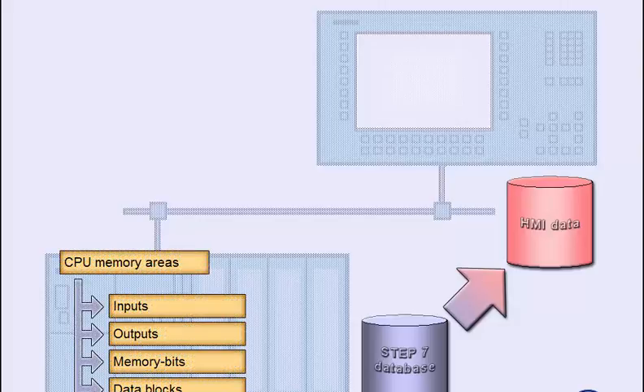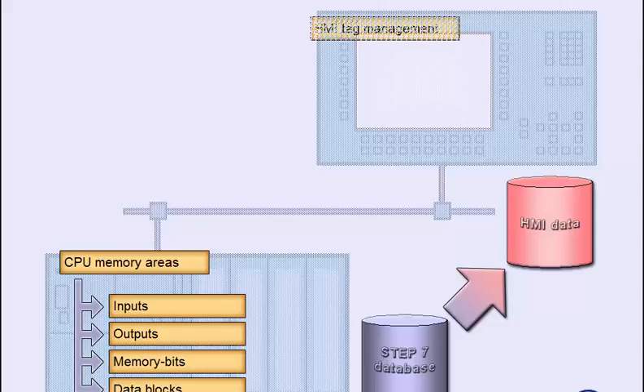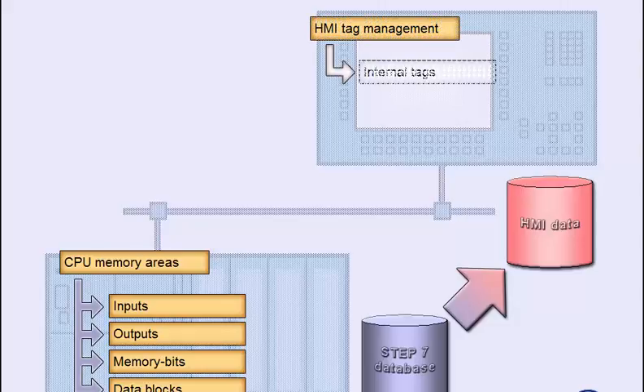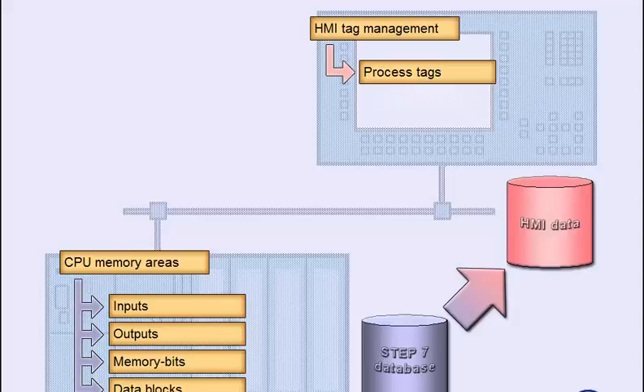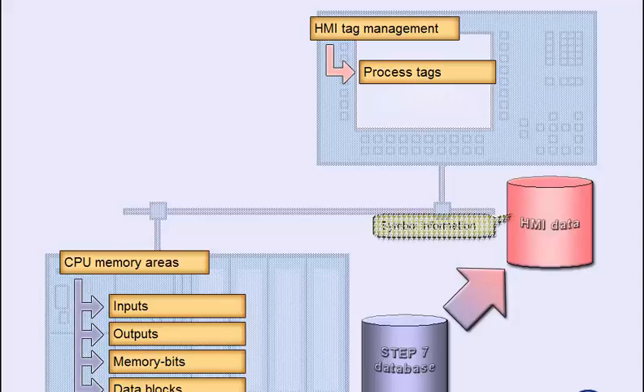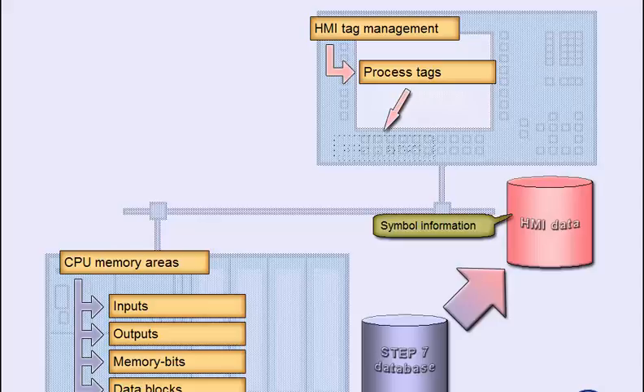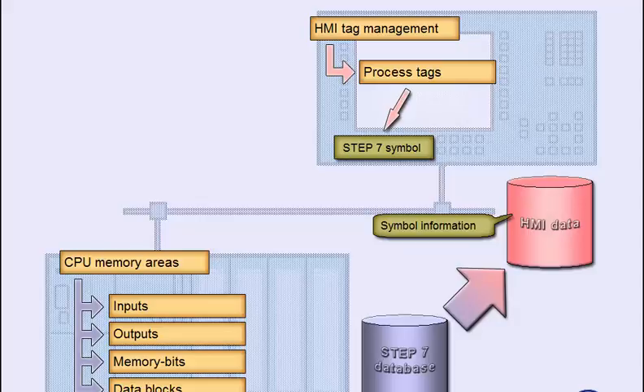Let us now look at the access to the controller's memory areas and thus to the process link. In the HMI system, data is transmitted by tags. Internal tags, as their name implies, are only valid within a specific HMI project. Process tags, on the other hand, do the real mapping of the controller's memory. The integration into Step 7 allows the allocation of the tag addresses in a symbolic way. The use of Step 7 symbols provides more clarity and reduces the risk of input errors.